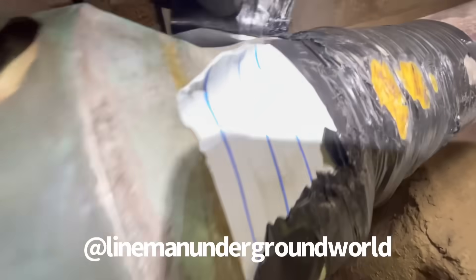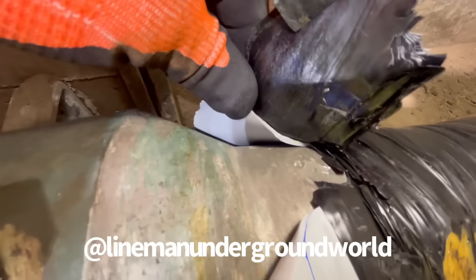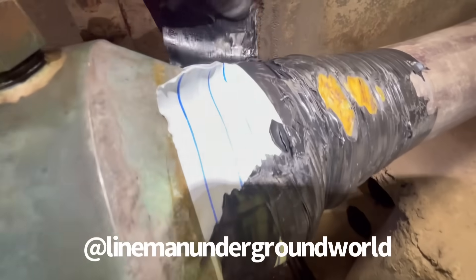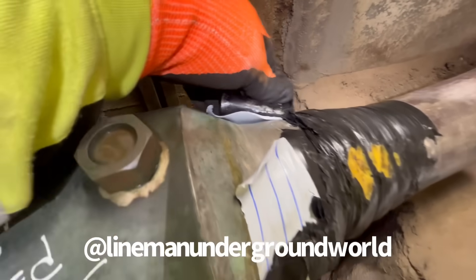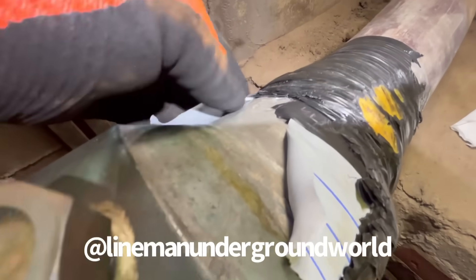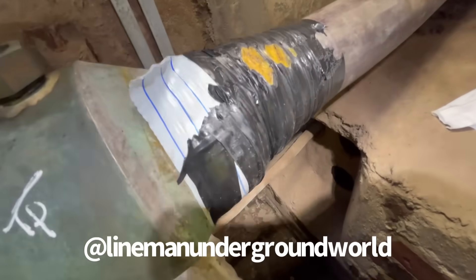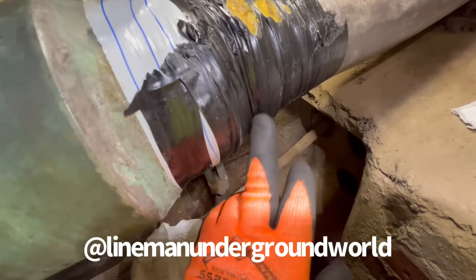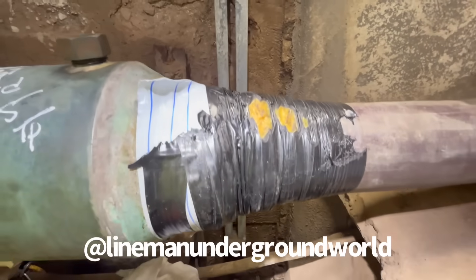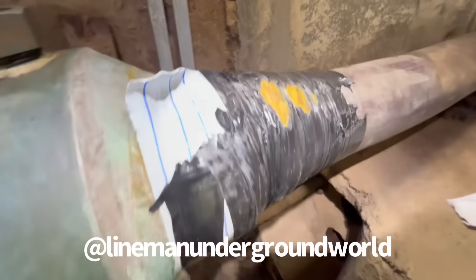What we're doing is taking the tape off — this was already busted inside the tape, that's why it's seeping, as you can see right here. We're going to take it off so we can just put some more tape on there. This is all the disturbance we're going to do for it — we're just going to re-tape it and tighten the boss nut back up and try to get it out ASAP. I believe it's cracked down here because of the type of stuff they put on there. I don't want to disturb it now. Sometimes you leave things alone to prevent making something worse.